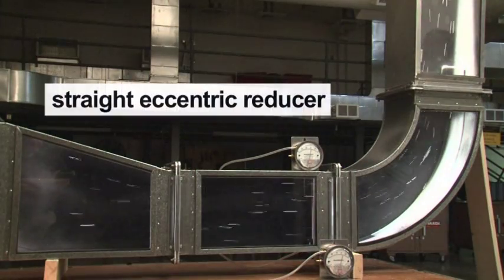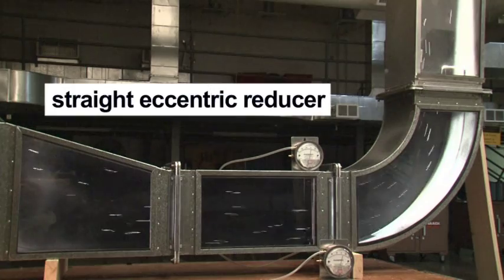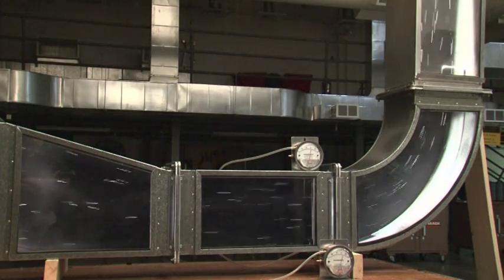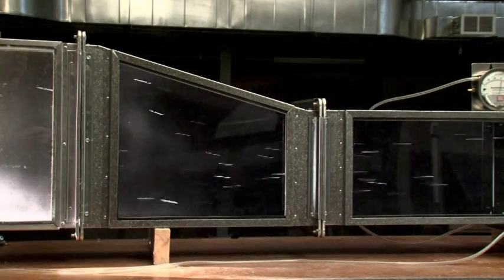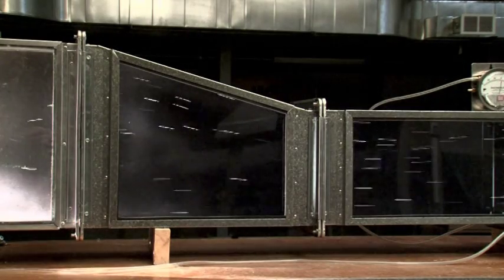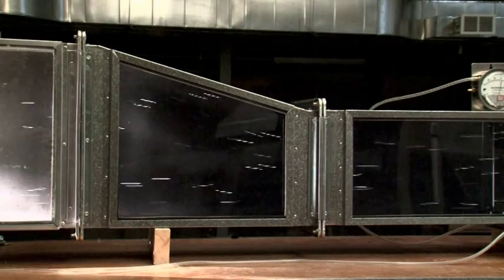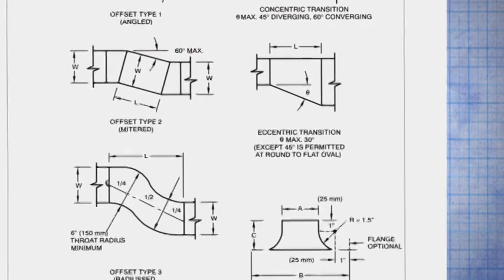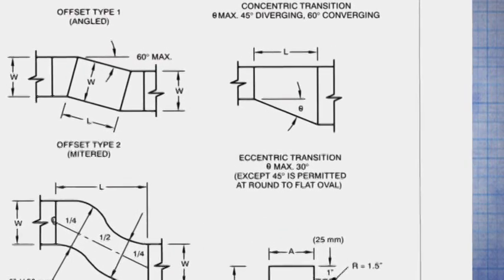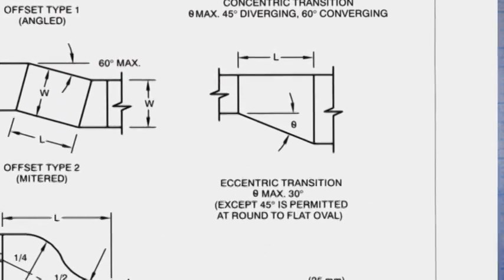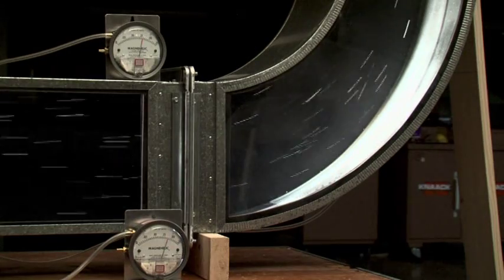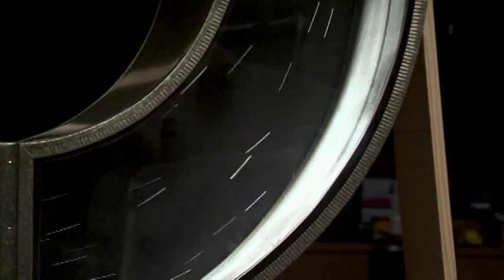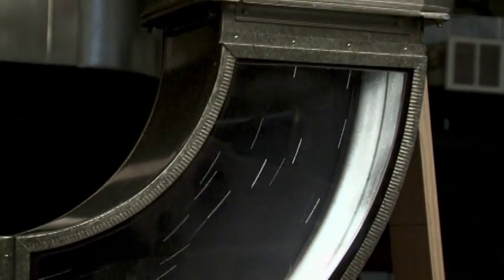This wide shot shows a straight eccentric reducer, a straight duct section, and a long radius elbow. The reducer changes dimensions over a fairly long length so that little turbulence is introduced — note the smooth airflow pattern. The reducer is easily within the recommendations for offsets and transitions in SMACNA's HVAC Duct Construction Standard. The long radius elbow is so designated because the throat has a large radius that provides a low resistance path for airflow.